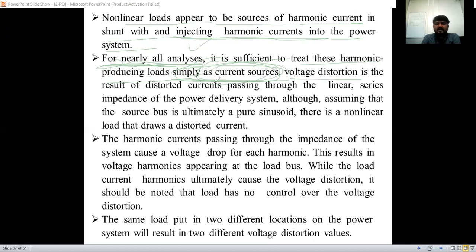So voltage distortion is the result of distorted current. If the current is distorted, because of that the voltage distortion will occur. The harmonic or distorted current passes through the linear circuit, the series impedance of the power delivery system, and that results in voltage distortion. Here we are assuming that the source bus is ultimately a pure sinusoid. Whatever the source bus is, we are going to consider the generator here.